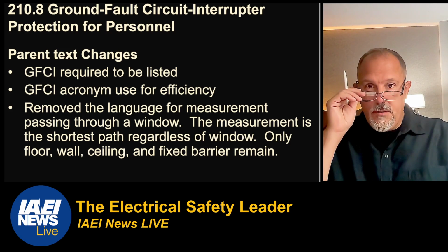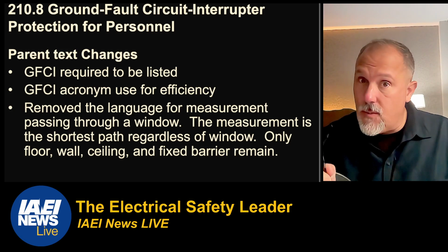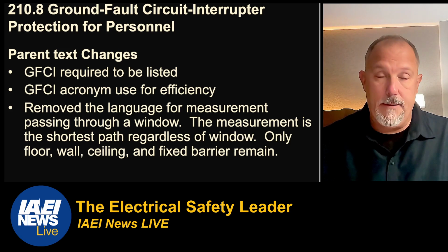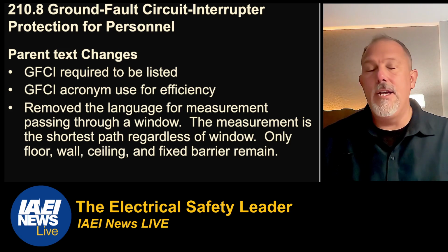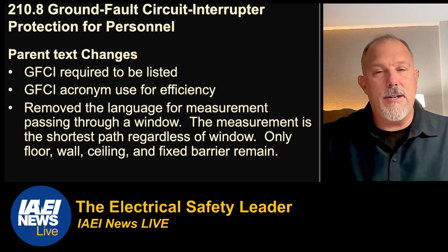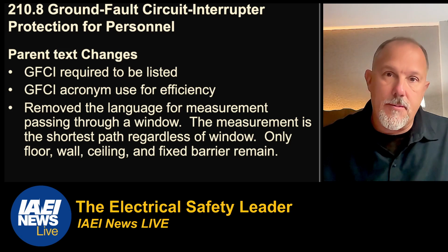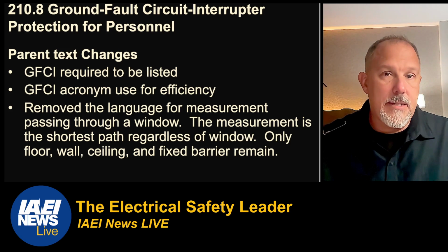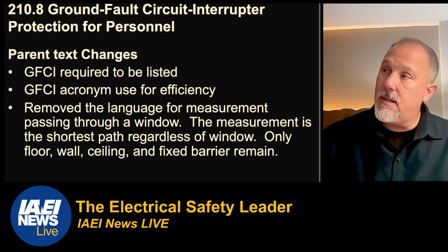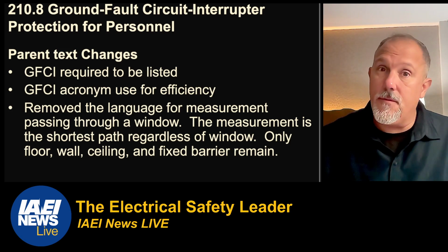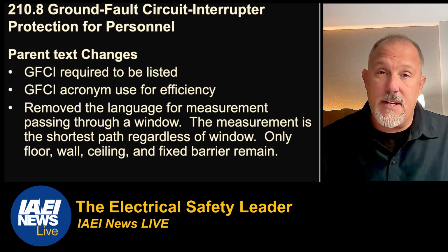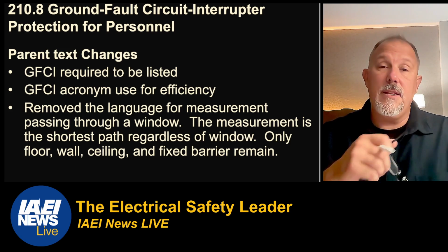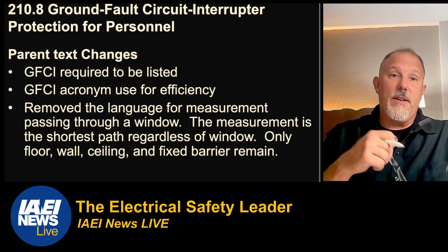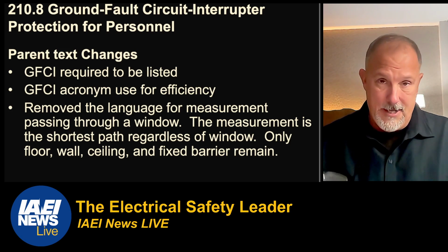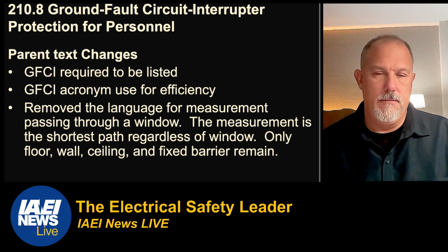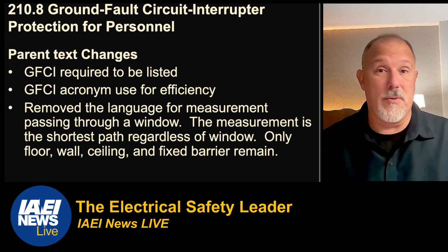So we removed window. And in the last cycle, remember, in 2020, we took out that whole concept of a doorway. The reason we had to address the door was because appliance garages have a door on them, and if there's a receptacle on the countertop within 6 foot of that sink, and it's inside the appliance garage, somebody could say the receptacle behind that door does not need to be GFCI protected. That was not our intent. Somebody could also say that the receptacle under the sink, because the cord would have to go through the door, does not need to be GFCI protected. So those examples made it confusing. And we said, look, we're just going to remove that reference to a door.